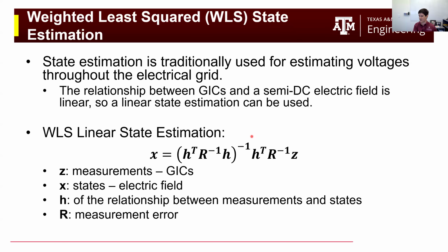In this case, it's a very underdetermined system. It's underdetermined in the sense that the number of unknown GIC flows in the system is much higher than the number of known GIC flows. However, since the system is connected, and if we have a decent model, which could always be improved for the real grid, we know that an E field is mostly uniform across a certain area, so the GICs can be calculated once you know the E field.